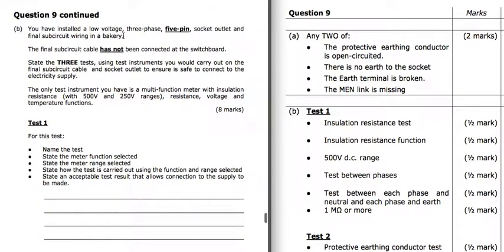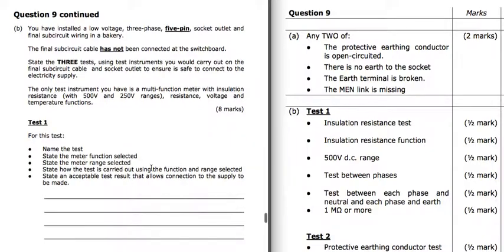We've installed a low voltage 3-phase 5-pin socket outlet and final sub-circuit in a bakery. It's not been connected to the switchboard yet, and we're going to do some testing, and we've got to do 3 tests. The only instrument you have is a multifunction meter with insulation resistance, so at least it tells us this time that we have got insulation resistance, 500 volts and 250 volts, and our basic other readings.